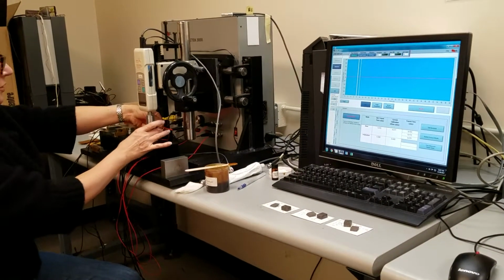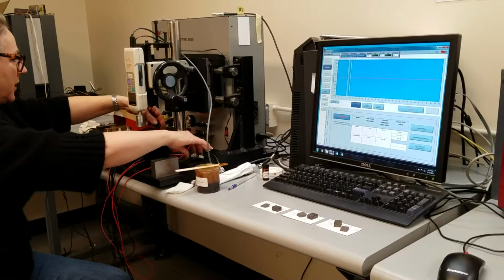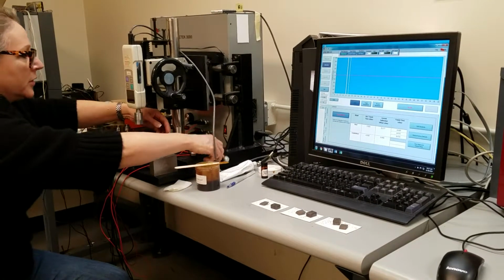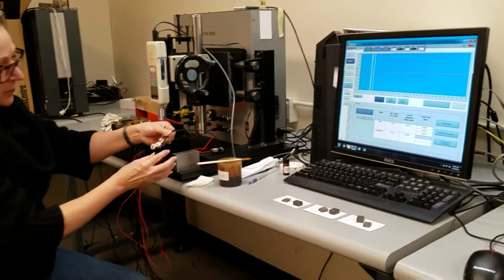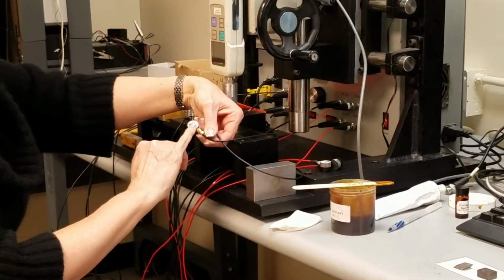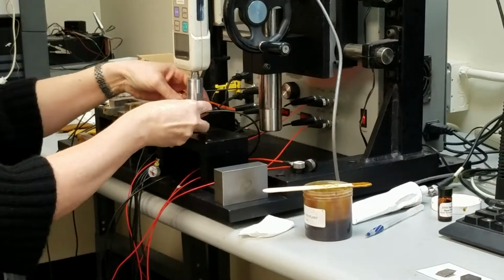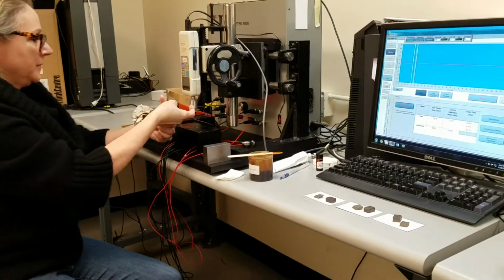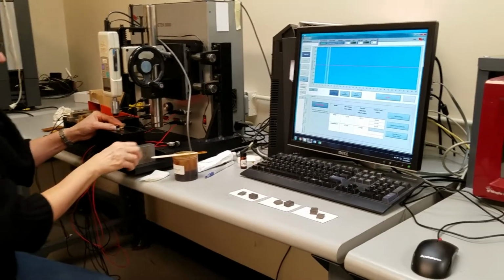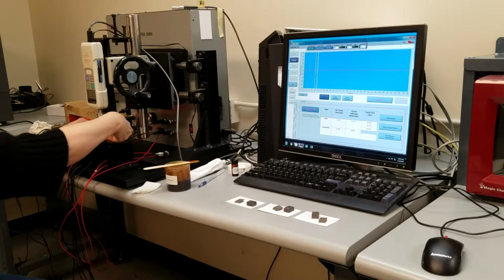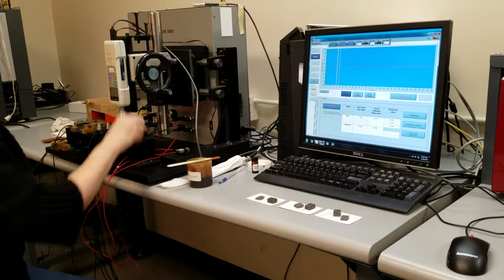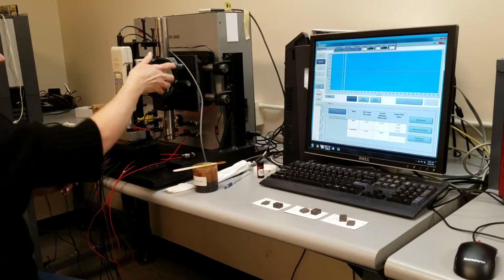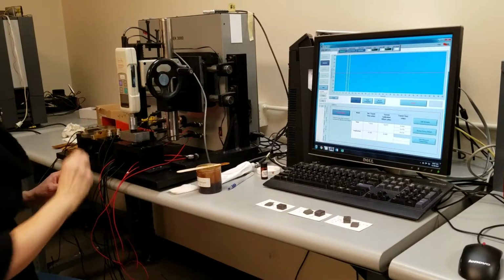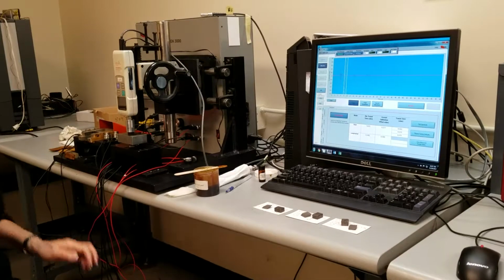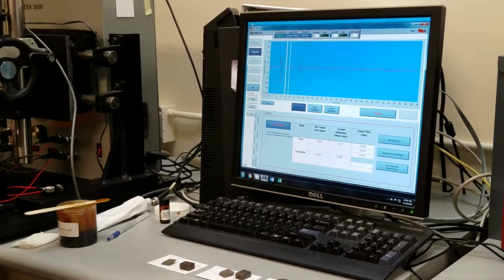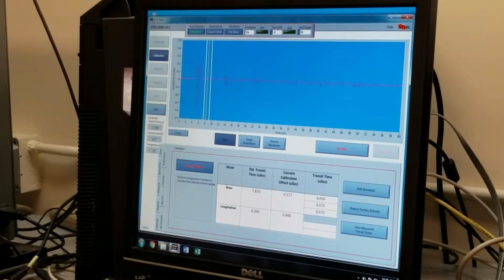I unscrew the set screw that is holding them in place, set the shear wave transducers aside, and put in the compressional transducers. To distinguish between the shear and the compressional, the serial numbers either start with a C or an S: C for compressional, S for shear wave. So now I will put my gauge block back into place and again apply about 700 newtons of load. The 700 newtons is not critical when we're dealing with materials other than friction material, but just for consistency's sake, we do 700 newtons.